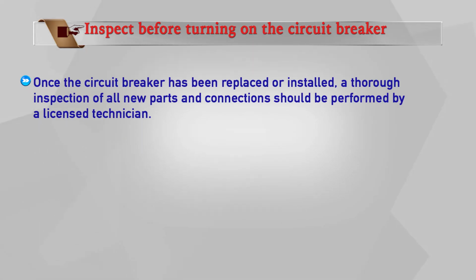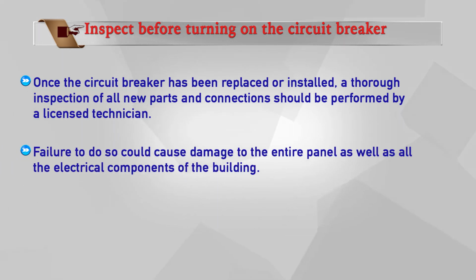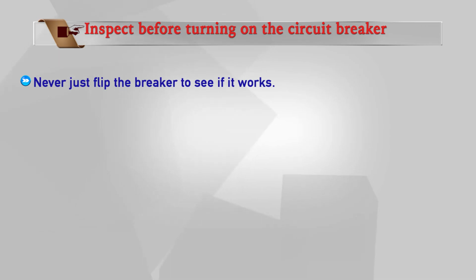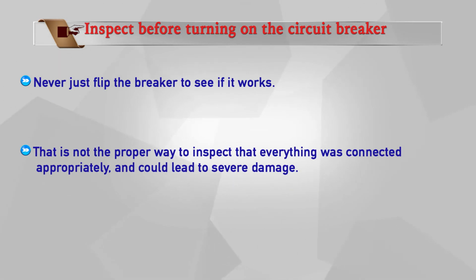Once the circuit breaker has been replaced or installed, a thorough inspection of all new parts and connections should be performed by a licensed technician. Failure to do so could cause damage to the entire panel as well as all electrical components of the building. Never just flip the breaker to see if it works. This is not the proper way to inspect that everything was connected appropriately and could lead to severe damage.